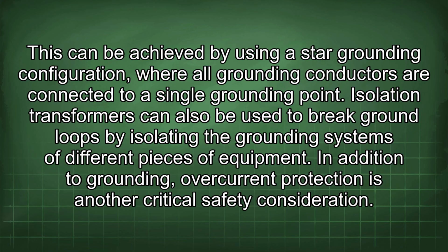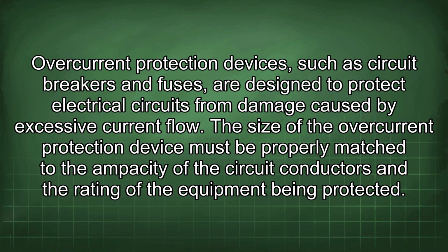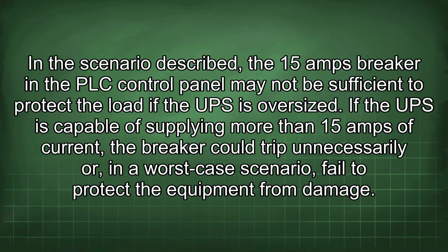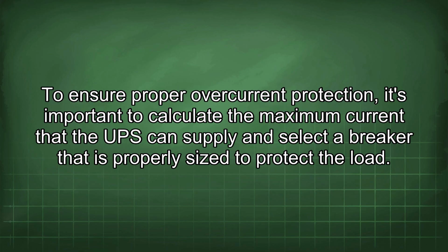In addition to grounding, overcurrent protection is another critical safety consideration. Overcurrent protection devices, such as circuit breakers and fuses, are designed to protect electrical circuits from damage caused by excessive current flow. The size of the overcurrent protection device must be properly matched to the ampacity of the circuit conductors and the rating of the equipment being protected. In the scenario described, the 15 amps breaker in the PLC control panel may not be sufficient to protect the load if the UPS is oversized. If the UPS is capable of supplying more than 15 amps of current, the breaker could trip unnecessarily or, in a worst-case scenario, fail to protect the equipment from damage. To ensure proper overcurrent protection, it's important to calculate the maximum current that the UPS can supply and select a breaker that is properly sized to protect the load.